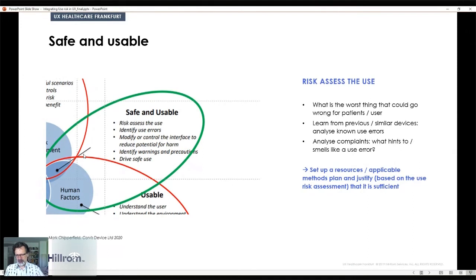If you're doing a class 1 medical device which basically cannot hurt anybody, you probably are okay when you do a limited amount of things. But of course, this is part of the process, so please document this and make, right at the beginning, a justified decision why you are putting those resources in here.